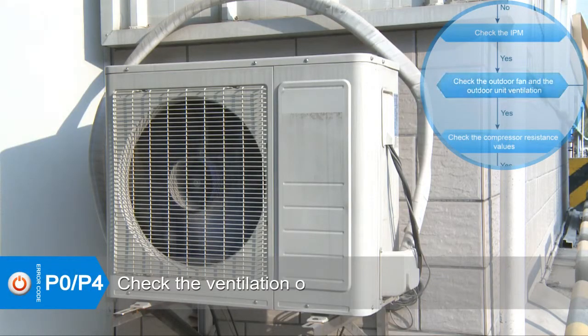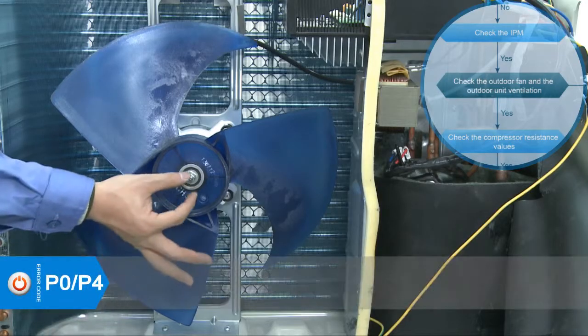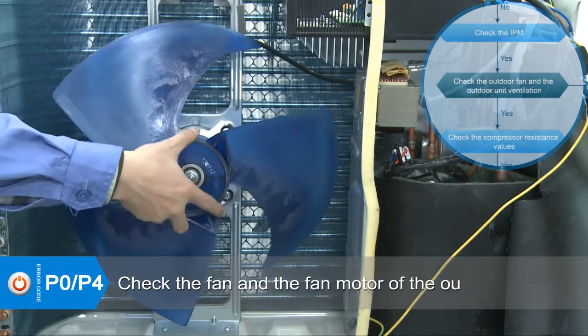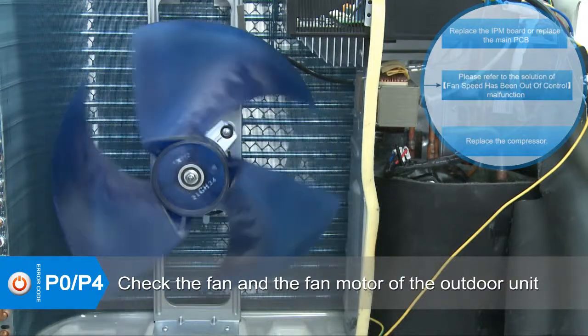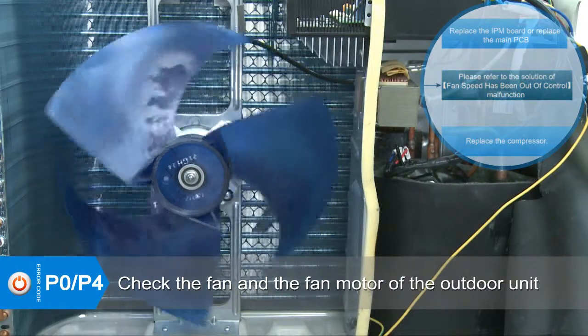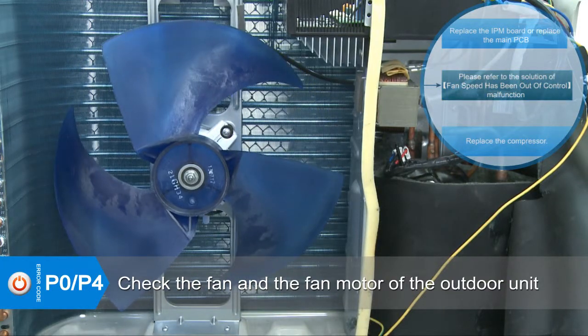Check if ventilation of the outdoor unit goes well. Check if the outdoor fan operates well, then find solutions according to the solution for the malfunction of fan motors being out of control.